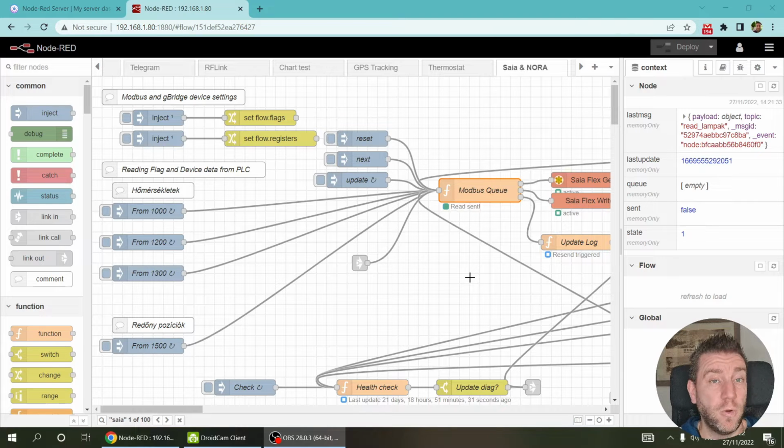I had all sorts of issues like connection issues and reconnecting issues, and I thought there was something wrong with the Modbus component within Node-RED. But it turns out that because I was using it for such a long time, probably from a very early version, I got used to using the Modbus nodes in a specific way. I was pointed out that there has been a lot of development in terms of reliability and fixing connection issues, and they are all related to a different set of nodes that you should use if you have problems like that.